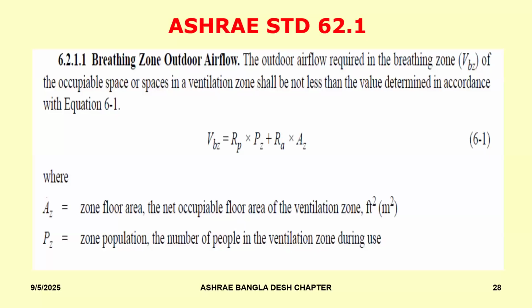But really the most definitive standard for ventilation and for breathing zone outdoor air is Standard 62.1. And I'm sure that all of you who are in ASHRAE and in HVAC practice are familiar with Standard 62.1. We can do a separate one-day program on 62.1. It is as wide and diverse. But what I'm going to tell you today is a few key features in 62.1, which all of us are probably familiar with, or should be familiar with, that help us arrive at the actual required ventilation airflow that is to be provided to each of the spaces.